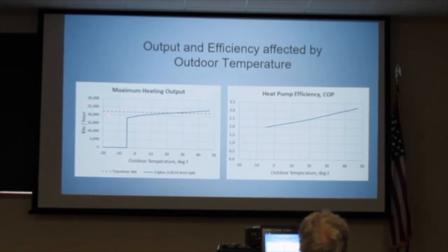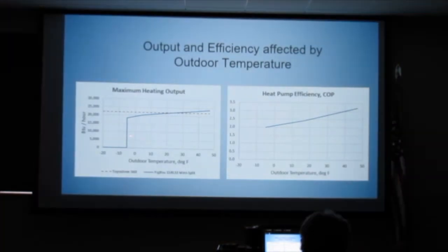So here's the output. This little line here is like a little Toyo stove - doesn't care what the outside temperature is, right? It can just go wide open independent of outside temperature. But a heat pump - this was the Fujitsu, manufactured data - shows the temperature from minus 20 to 50, and how your output drops ever so slowly, constantly, and at minus 5 that was their rating, so they stopped giving us any data. In reality, it continues down this curve for, I don't know, minus 15. I think at Fairbanks they've run down to minus 20. I assume at some point the refrigerant doesn't boil anymore, so there must be some number down there where they don't work. But for us, this is certainly more than sufficient for Seward's climate.